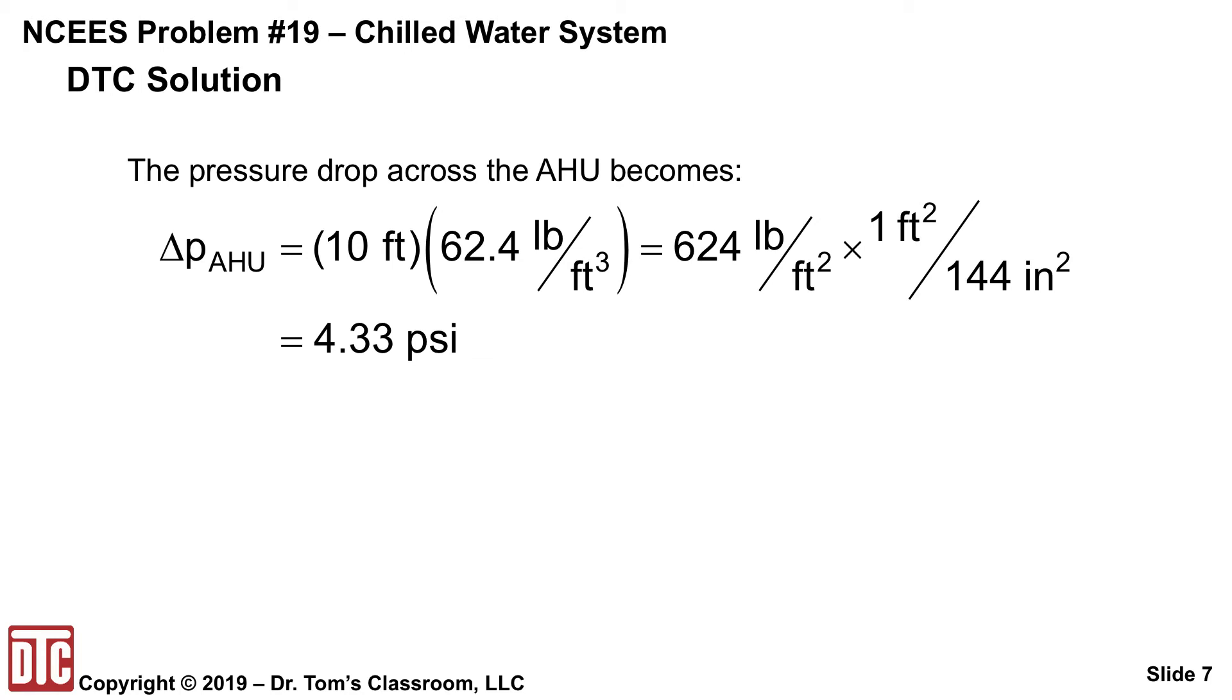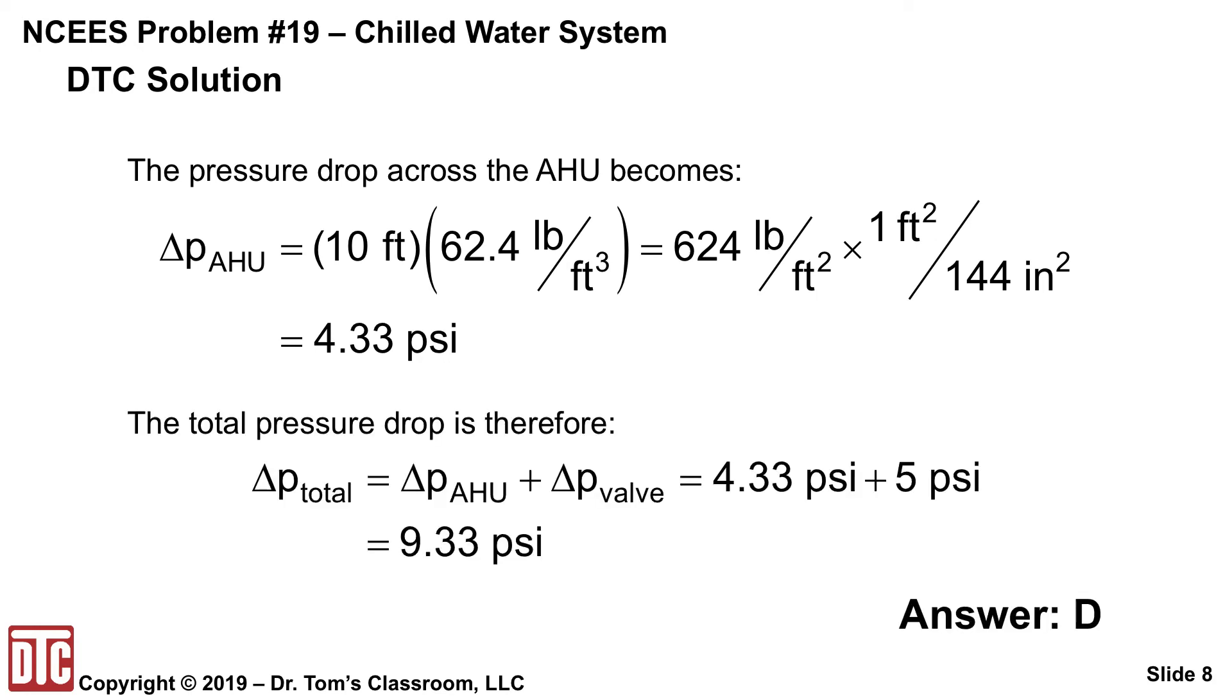So you've got 10 feet times 62.4 pounds per cubic foot, which gives you 624 pounds per square foot, which you need to convert to PSI. When you do that, you get 4.33 PSI. And so just add the 5 PSI for the valve and you get 9.33, and that's answer D.